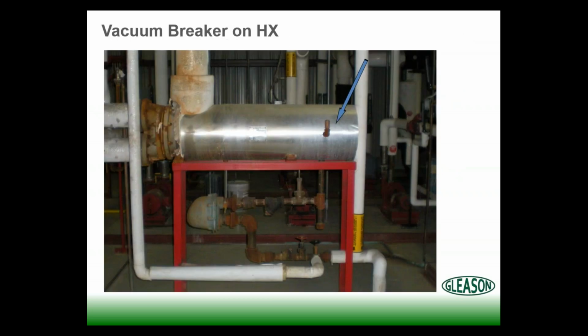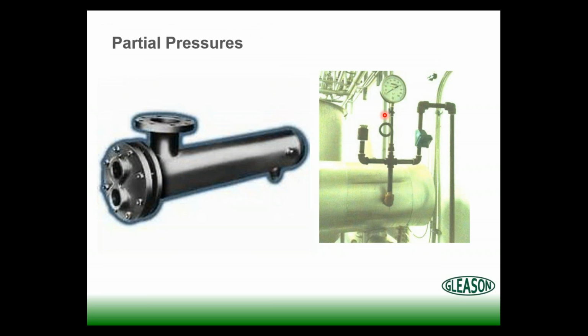Let's put our vacuum breaker there. Here's another vacuum breaker there at the arrow. We have what we call Dalton's law of partial pressures. For example, steam at 100 psi is 338 degrees Fahrenheit, according to the steam tables. If we have a mixture that's 20% air, then Dalton's law of partial pressures says that our temperature is going to be reduced by about 20%. So if you're showing pressure on a heat exchanger and you're not getting your temperature, very good chance you could have air there. So we have an air vent.